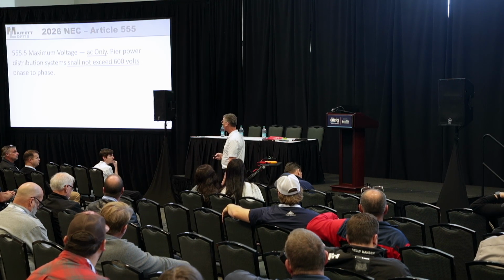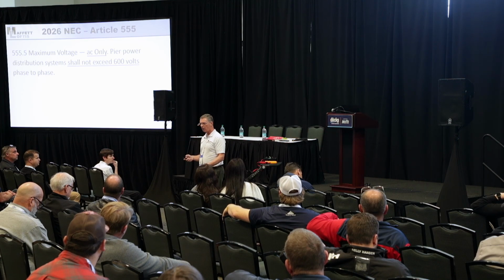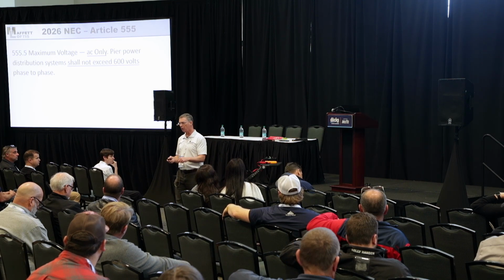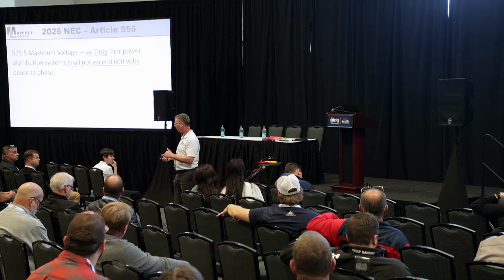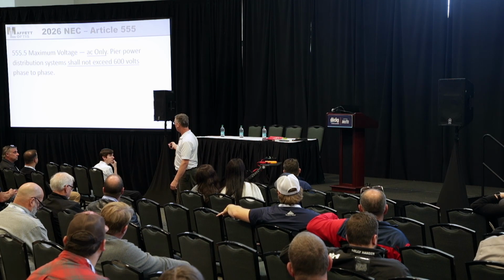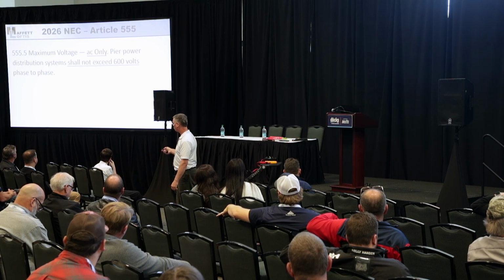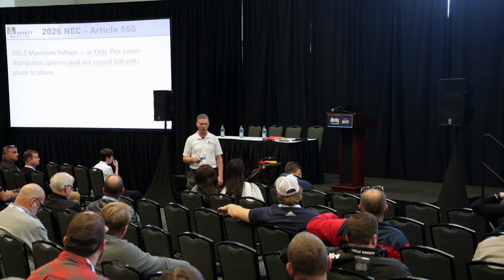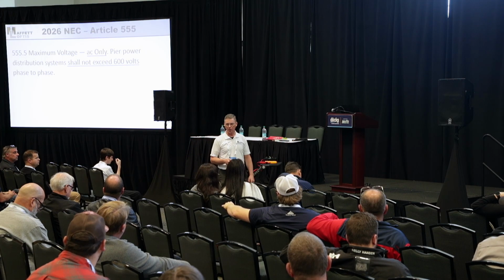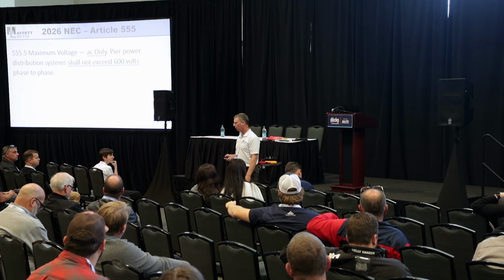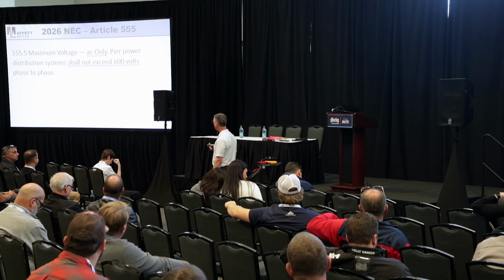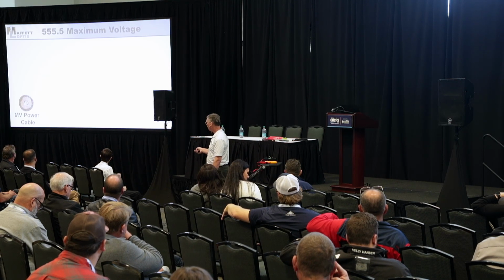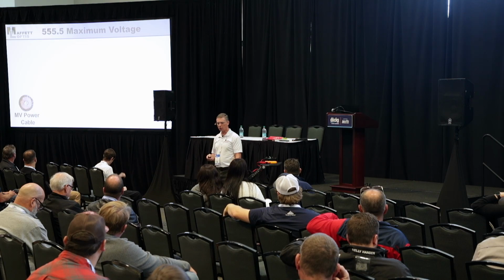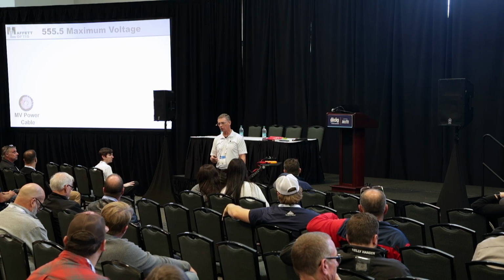AC, phase to phase, there's a limit of 600 volts. In Tennessee there's no limit, and in Kentucky there's no limit on voltage, because Tennessee and Kentucky have, in their legislative process, eliminated this requirement from the NEC. So if you look here, I can put in medium voltage systems in Tennessee and Kentucky, and I am doing it. This is why.